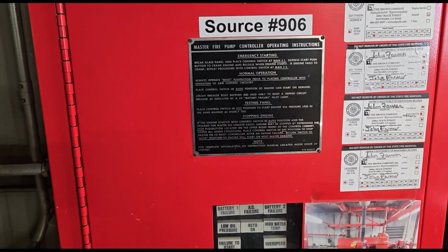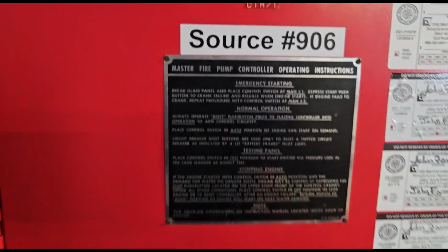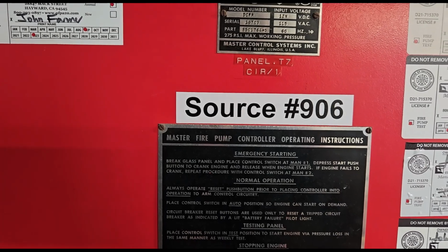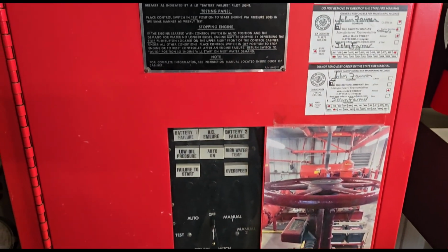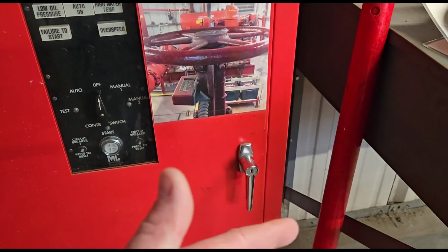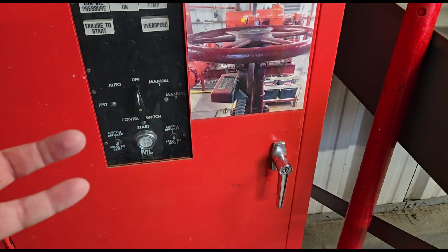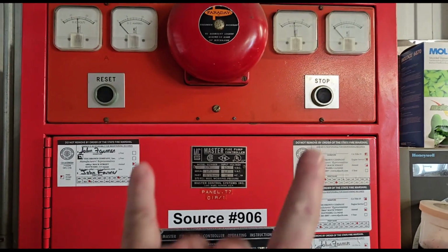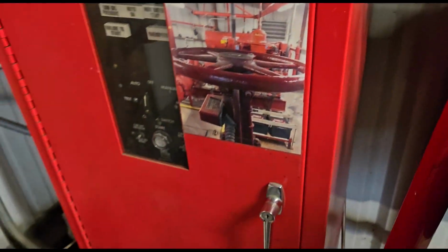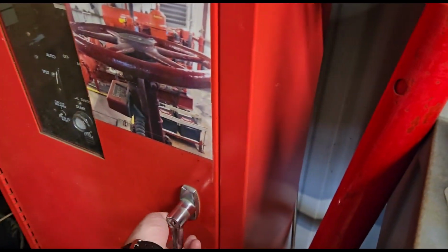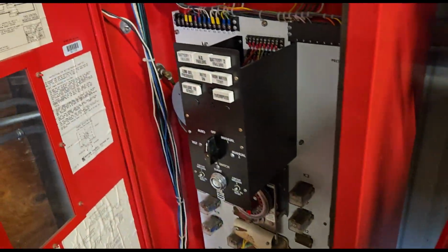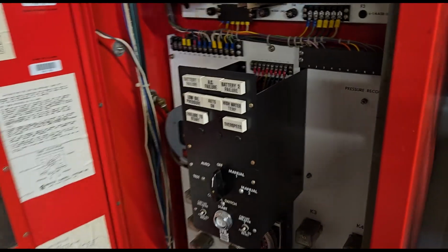So now we're back at the controller. This is the master fire pump controller, or Master Control Systems. We're going to open the door up and turn it back on. Obviously, if something were to kick on, I have my stop and reset. So I'm going to stand off to the side and open the door. Again, I'm not wearing an arc flash suit, so I'm doing this at my own risk.